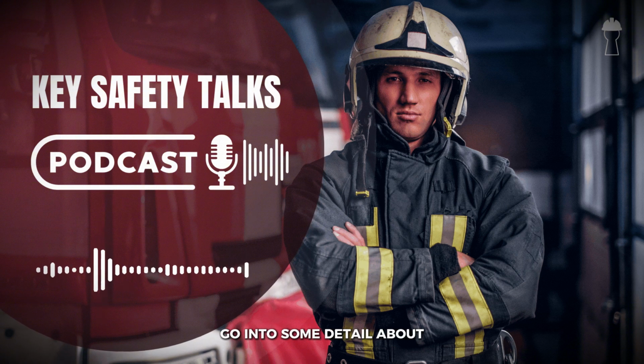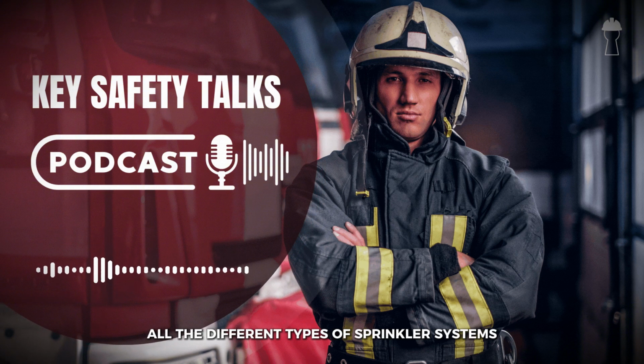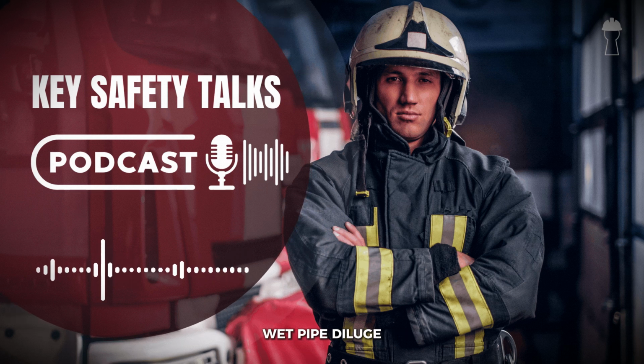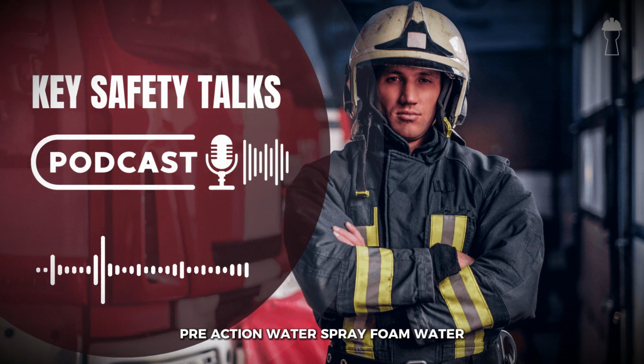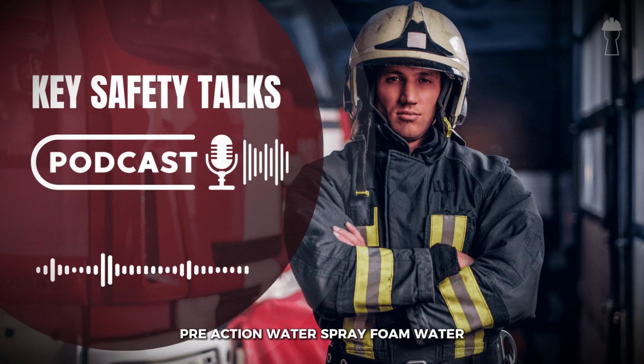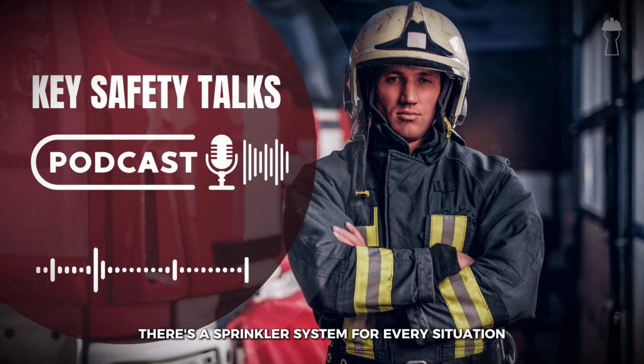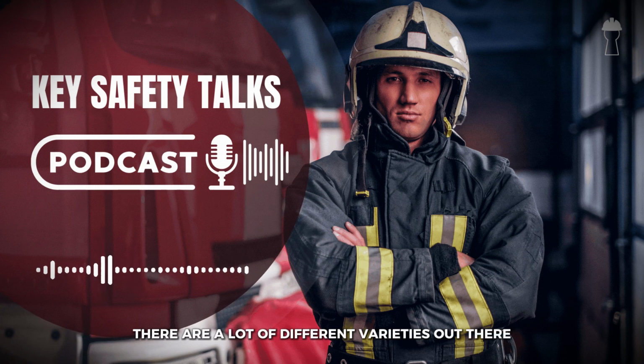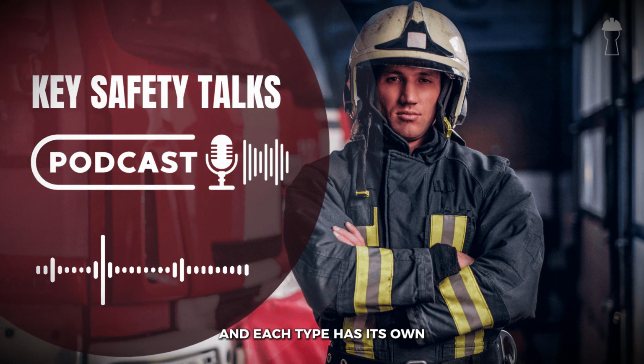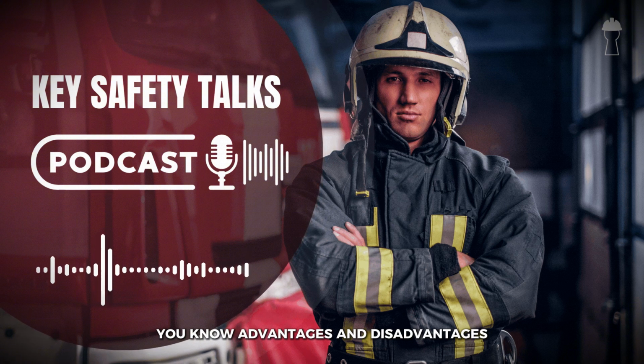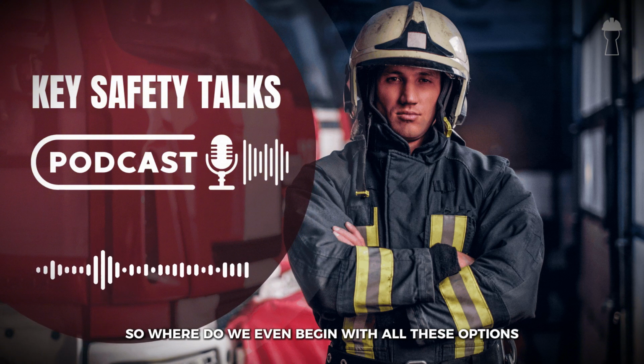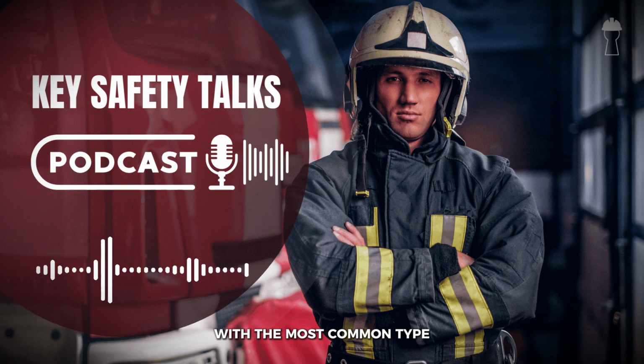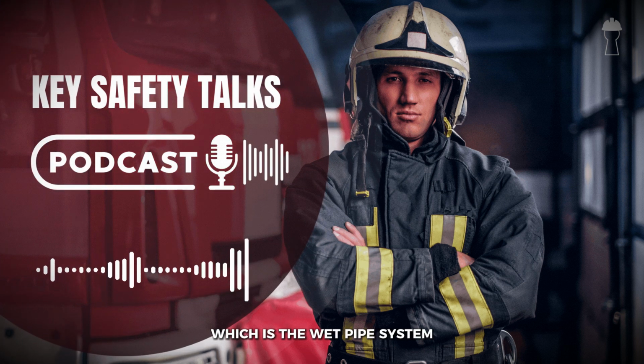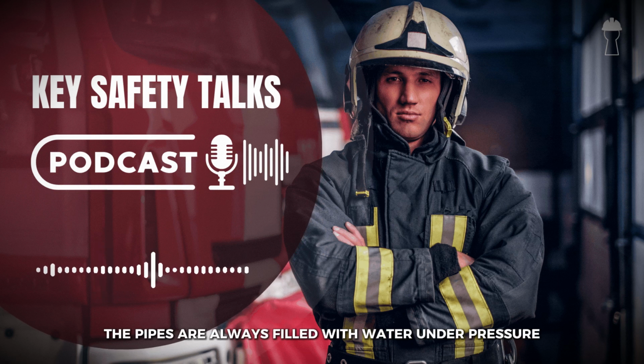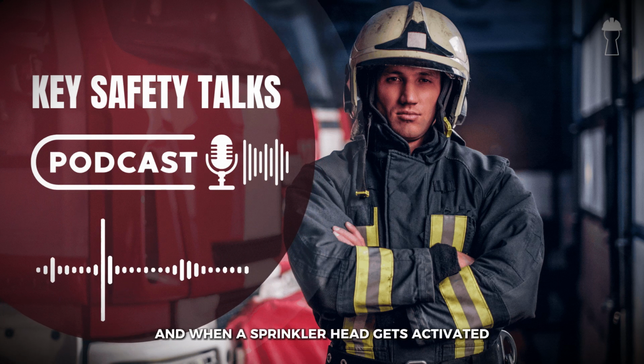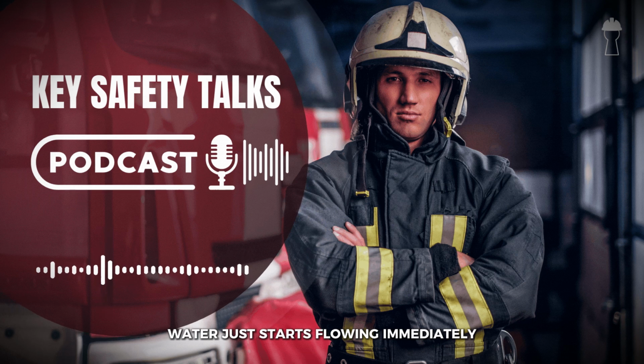Now, our sources go into some detail about all the different types of sprinkler systems out there. We've got dry pipe, wet pipe, deluge, pre-action, water spray, foam water. It seems like there's a sprinkler system for every situation. Yeah, you're right. There are a lot of different varieties out there, and each type has its own advantages and disadvantages. So where do we even begin with all these options? Well, let's start with the most common type, which is the wet pipe system. It's pretty simple, really. The pipes are always filled with water under pressure, and when a sprinkler head gets activated, water just starts flowing immediately.